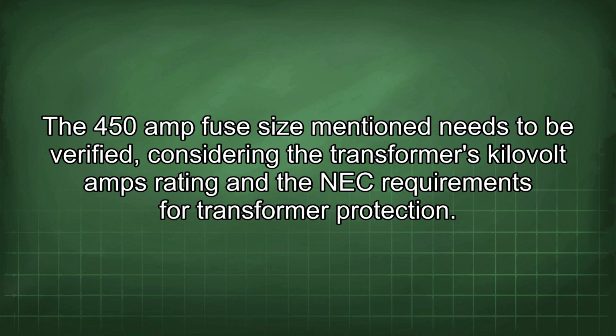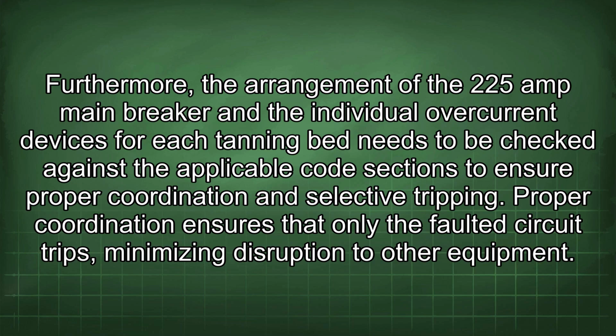Furthermore, the arrangement of the 225 amp main breaker and the individual overcurrent devices for each tanning bed needs to be checked against the applicable code sections to ensure proper coordination and selective tripping. Proper coordination ensures that only the faulted circuit trips, minimizing disruption to other equipment.